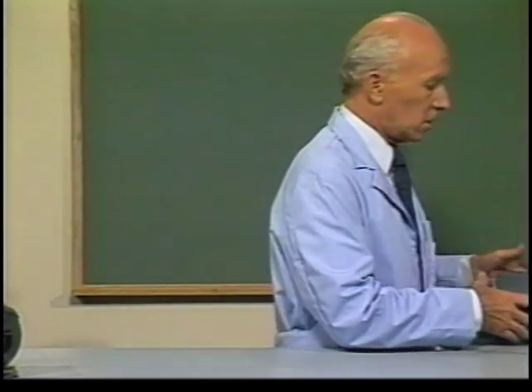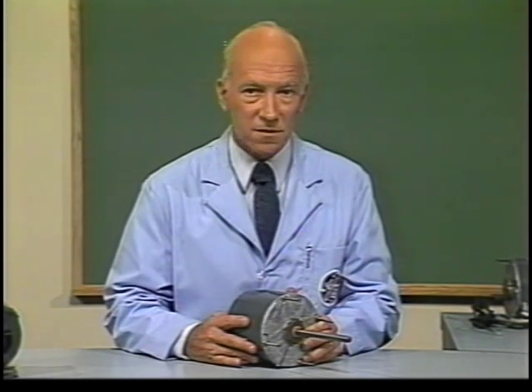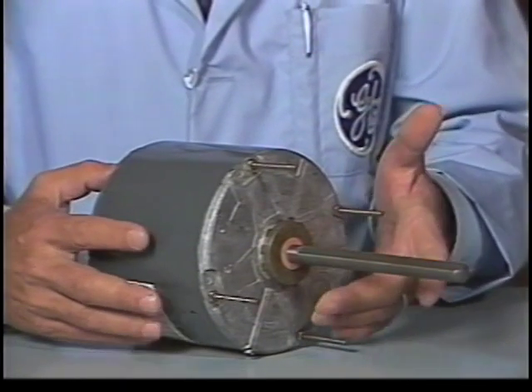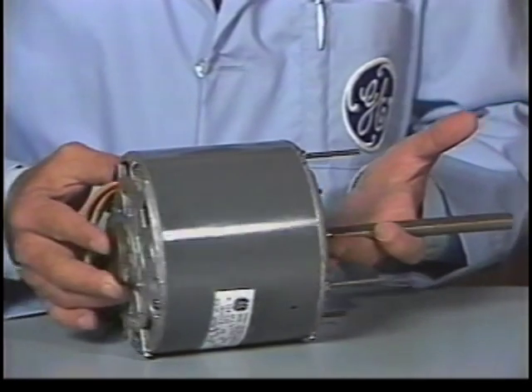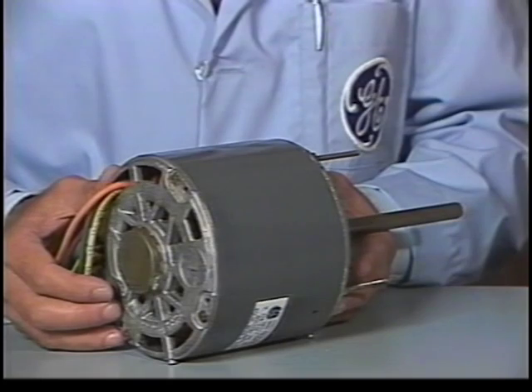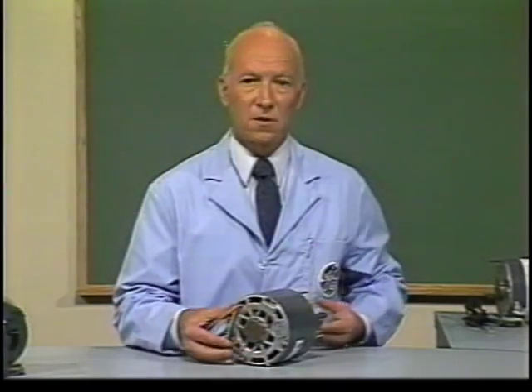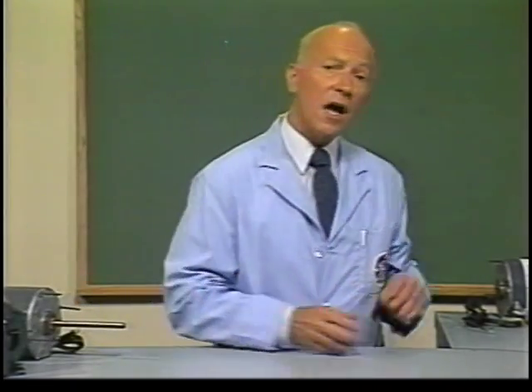The third type of motor enclosure is known as partially enclosed. This enclosure is used where portions of the motor may be exposed to outside elements. In this example, one end shield and the motor shell are closed providing the needed protection; however, the other end shield does have ventilating openings to allow external cooling air to reach the motor windings.